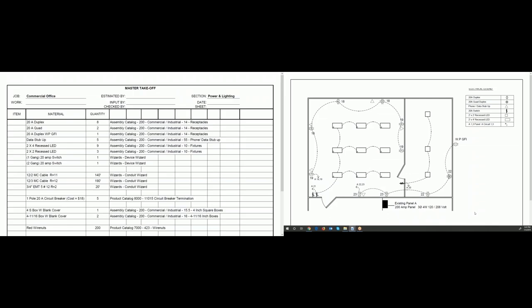Another important thing is counting the number of runs of conduit. A run of conduit is defined as from a device to a fixture or from a fixture to a fixture. Each segmented line on the drawing represents a run. You'll want to know the number of runs because when you input using the conduit wizard, it shows two connectors per run. The 12-2 MC cable has 11 runs, 140 feet total. The 12-3 had 190 feet total and 12 runs.